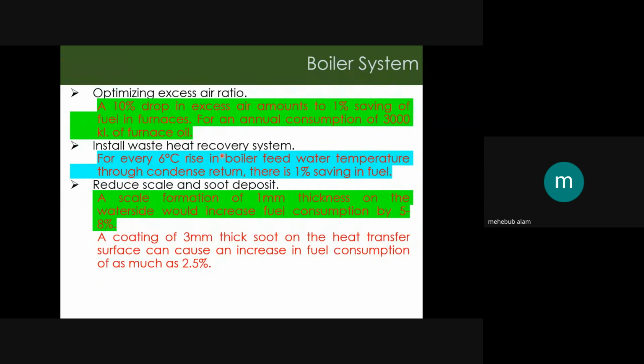In a similar fashion, the water is being converted into steam by the energy obtained from that coal, and that water is being poured through the boiler into the different tubes, and over time the soot will be deposited in the tubes. So we have to reduce that scale and soot deposition, because a scale formation of 1 millimeter thickness on the water side wall or tube will increase the fuel consumption by 5 to 8%.